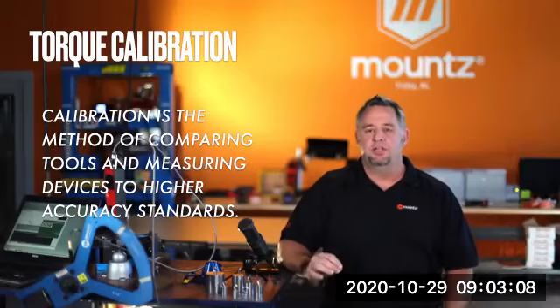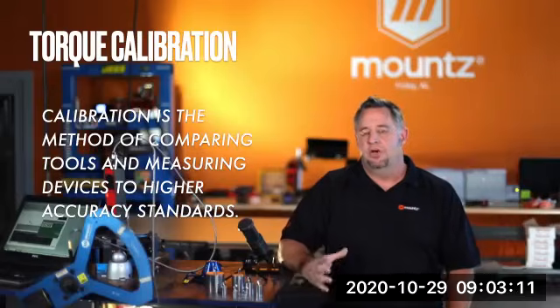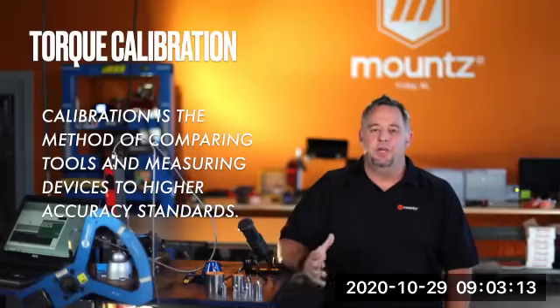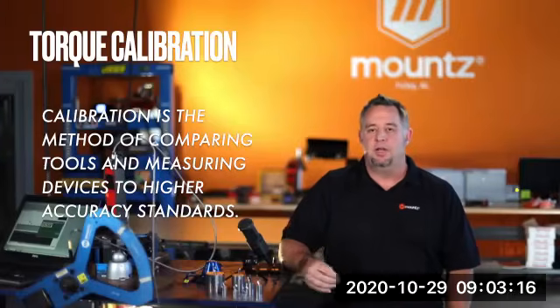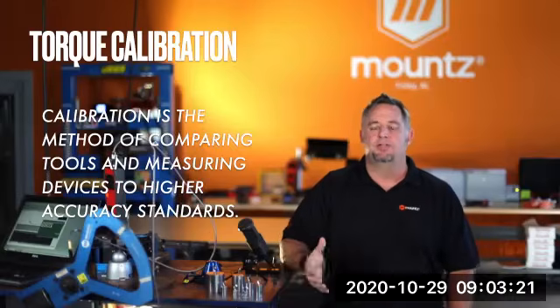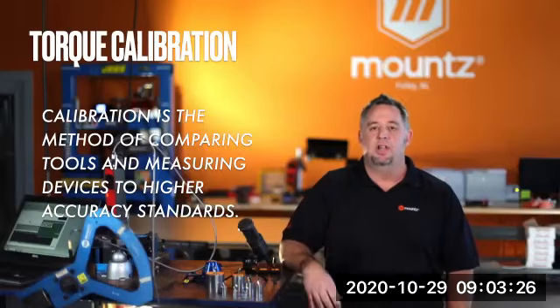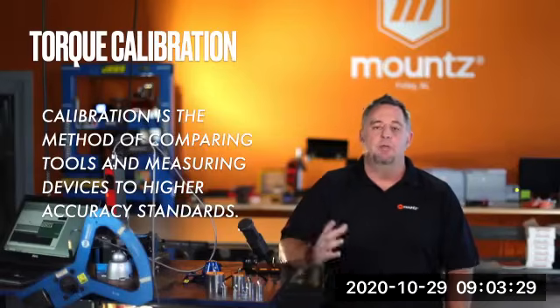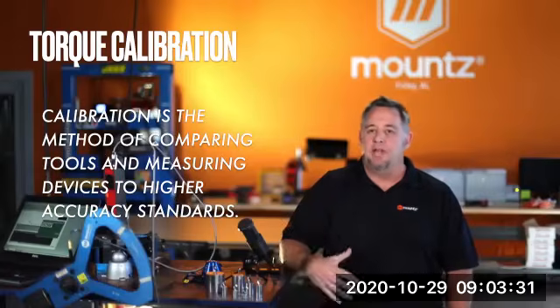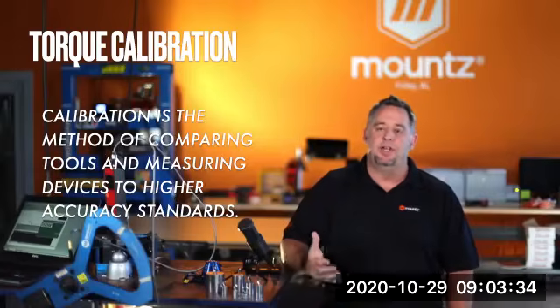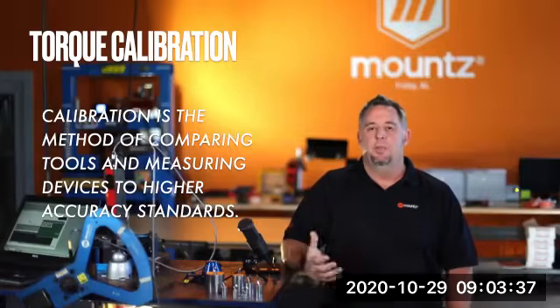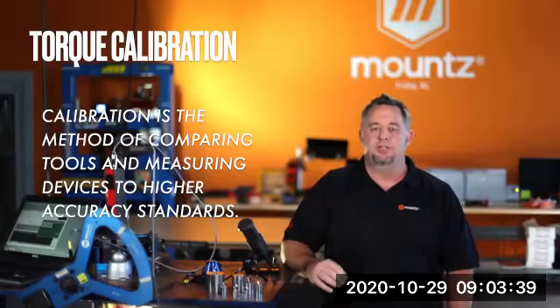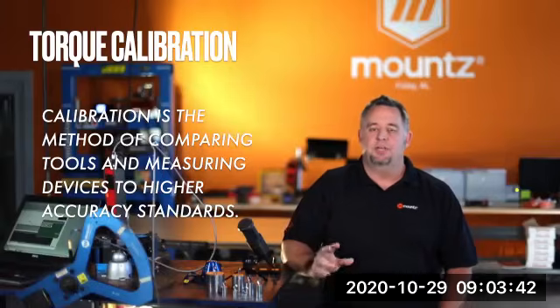Now there is a little distinction between the two. The torque analyzer is the portion of the unit that is handling the display, the calculations from the sensor itself. Often we do have sensors that are built into a torque analyzer. For example, our LTT product has the analyzer, the transducer built into it. We also have a handheld analyzer, our PTT unit, that you add sensors to. That is a very portable type of system.